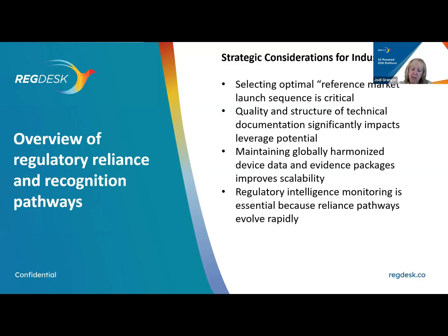Manufacturers should also prioritize global harmonization of technical documentation, meaning make sure that when you're pulling together your design requirements, your validation and verification requirements, what standards you're going to be complying with, all of that needs to be factored in with a global worldview. Companies often trip up here where they decide that their reference market is going to be the US and EU, and they only focus in on the requirements in that market and assume that because there are reliance pathways, that they are going to be able to move to these other markets more quickly. But if they have not factored in specific requirements for each of those countries, then they may hit a stumbling block when they submit for a reliance pathway.